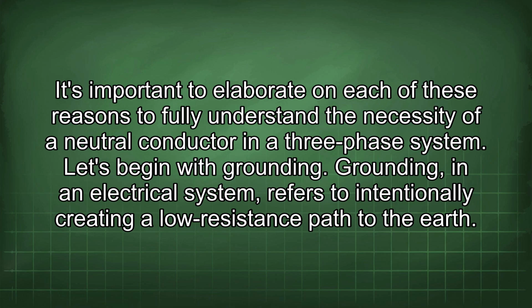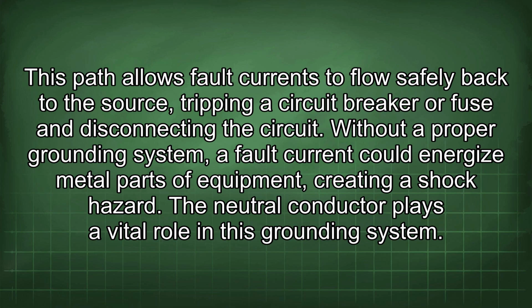It's important to elaborate on each of these reasons to fully understand the necessity of a neutral conductor in a three-phase system. Let's begin with grounding. Grounding in an electrical system refers to intentionally creating a low resistance path to the earth. This path allows fault currents to flow safely back to the source, tripping a circuit breaker or fuse and disconnecting the circuit. Without a proper grounding system, a fault current could energize metal parts of equipment, creating a shock hazard.